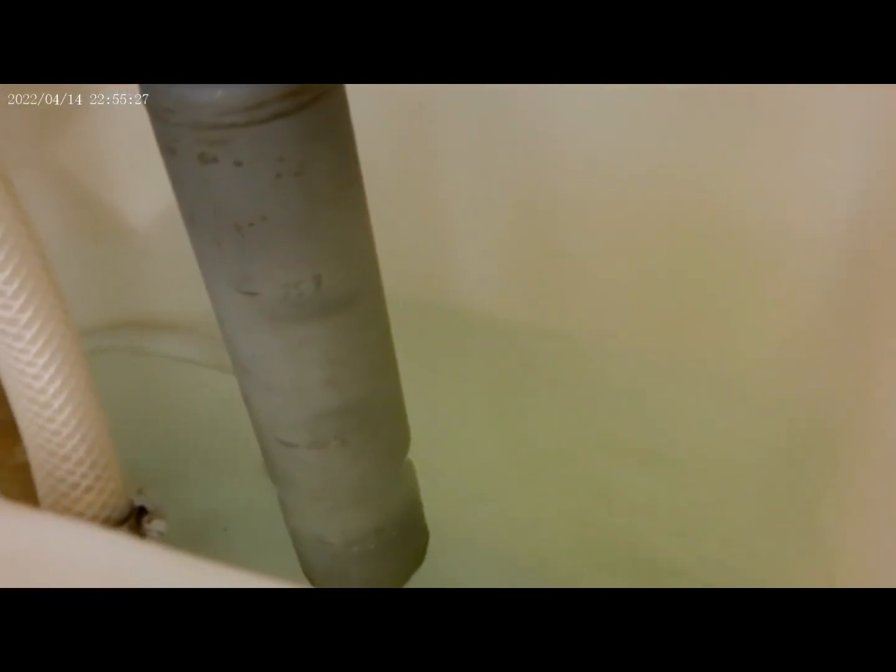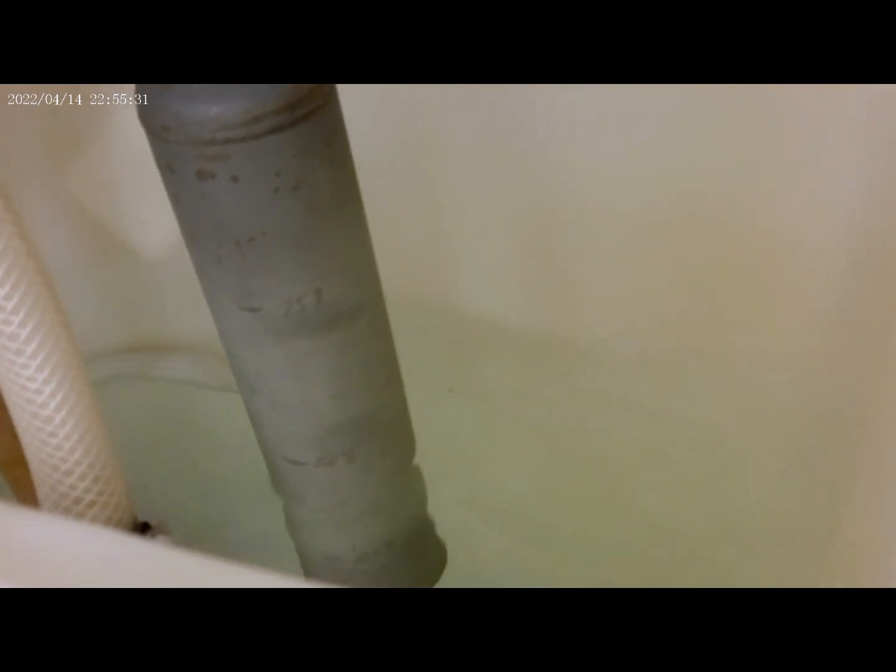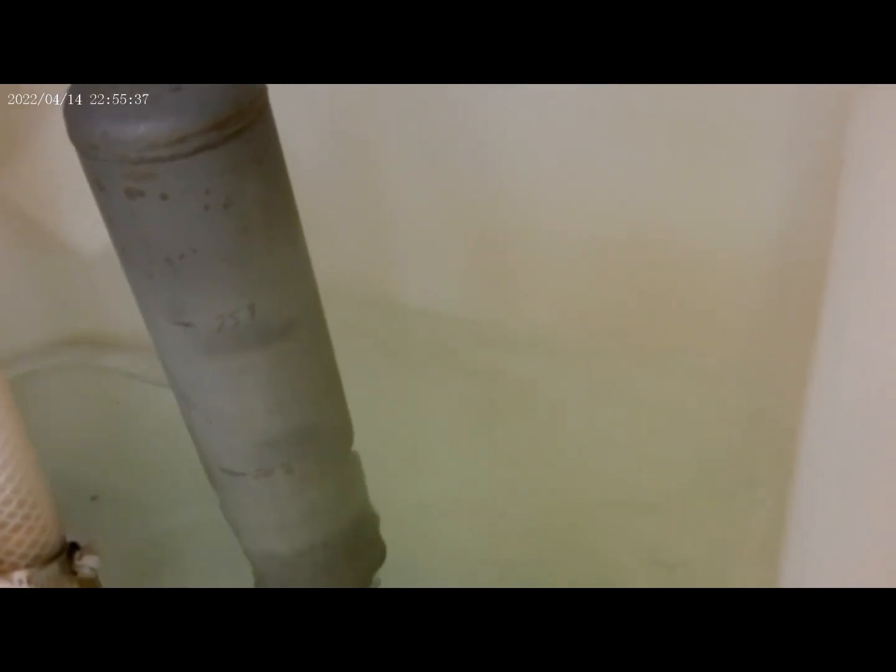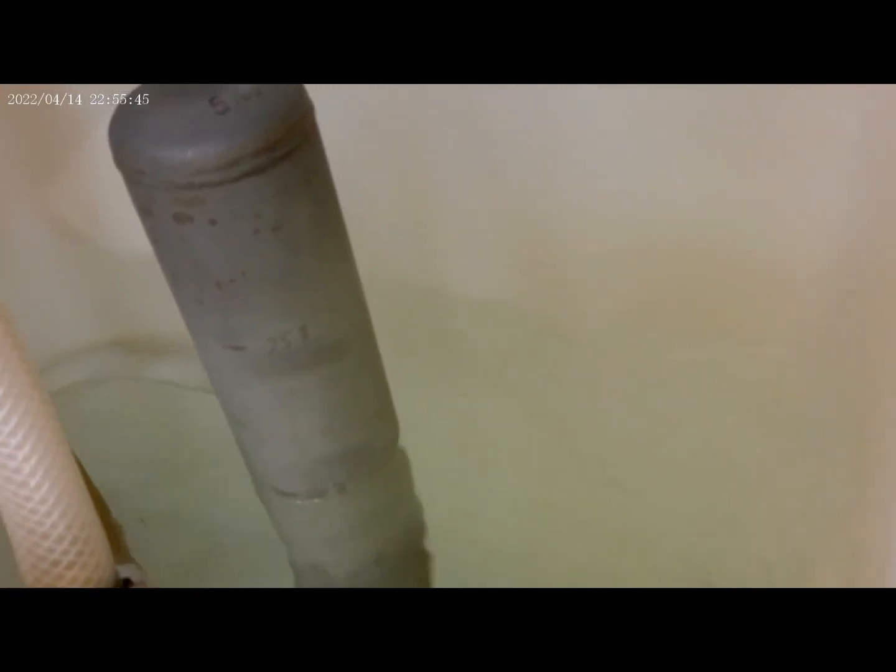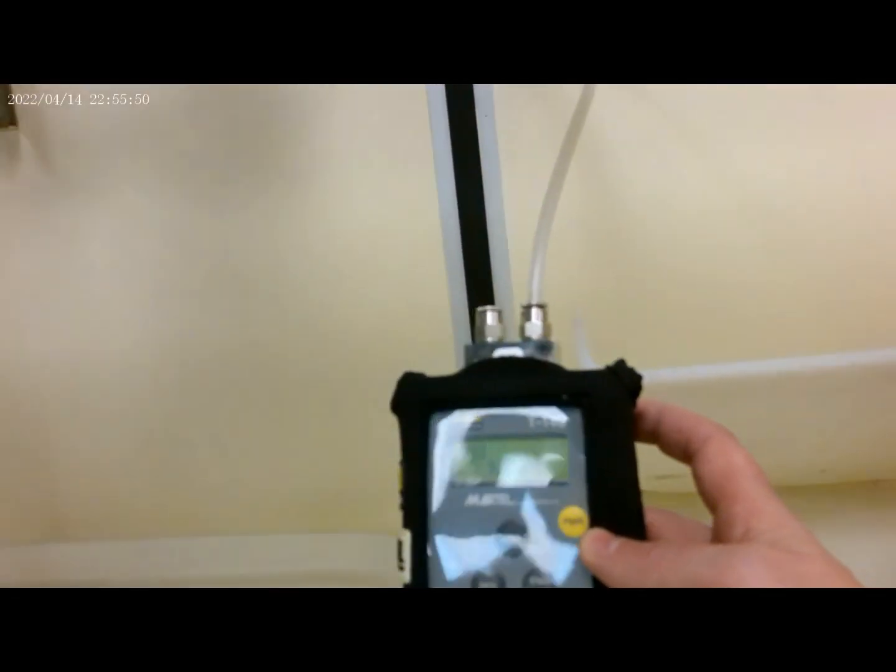Our output actually is past 25%, we're coming up closer to 50%, we're about 40%. I know this is fairly slow, it's a big tank. So we're coming up on 50% right now and we're just about there. Right now we're at 50% and we have pretty much 9 psi output which is 50%, and we can see that up here as well.